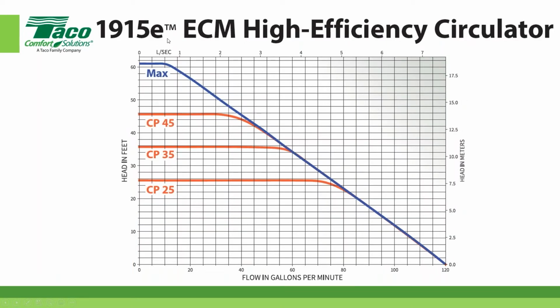This is one of our high efficiency circulators, used up into a light commercial application, the 1915E. Let's put an operating point on there that we know. Pretty easy, 20 gallons a minute at 20 foot of head. I want to know what additional resistance the system is going to impart on the circulator if I just raise the GPM up to 30 gallons a minute. I'm just going to raise it 50%. One might think, well, if you raise the flow by 50%, the head's going to go up by 50%. So we're going to end up over here at 30 and 30. Does that make sense to you?